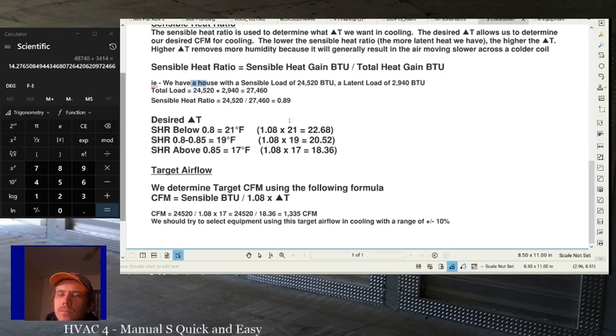So based on our sensible heat ratio, we can determine our desired delta T. All right. So our desired delta T, if our sensible heat ratio is below 0.8, then we want a 21 degree delta T. So this would mean that at least 20%, right? At least 20% of our load is latent, and then the other 80% is sensible. So 20% or 21% or 30% for that matter is a pretty high latent load. So we want a higher delta T to remove that latent load. And this is here to cheat later. This 1.08 times these numbers is there to just get a cheat number later. So you have it. We'll talk about that shortly.